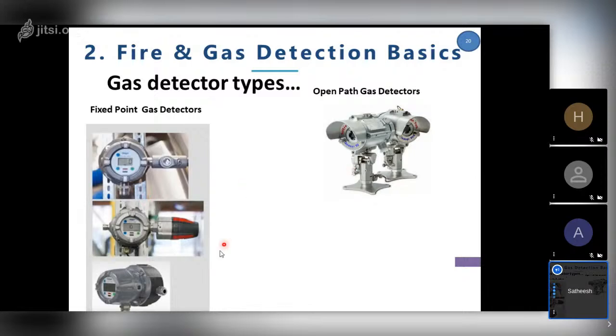You put a lot of point gas detectors around, and use these open path gas detectors only for boundary protection, like a fence. For example, imagine this slide is a plant. You keep one transmitter here, one receiver here, one over here, one over here, so that you protect this entire asset. And in between, where there are a lot of leak sources, you can put the point gas detectors. The path length can start from 5 meters to 200 meters. So you can have such a big fence of gas protection.